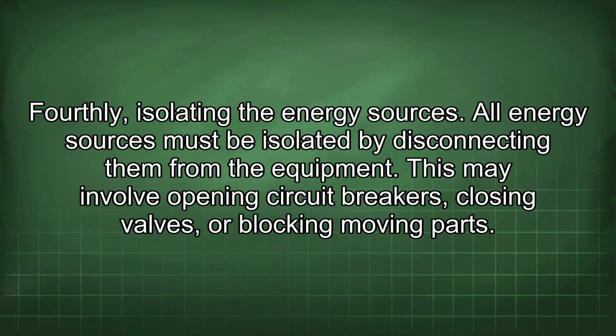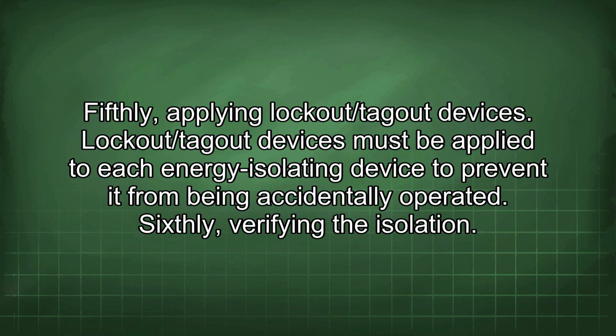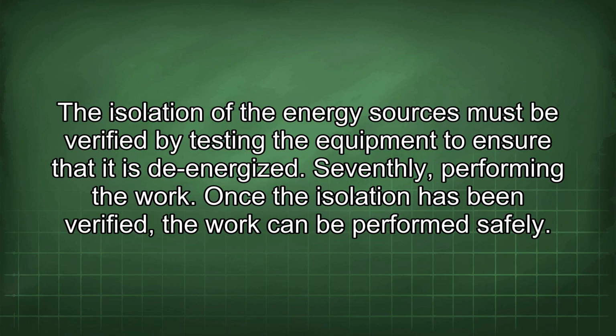Fourthly, isolating the energy sources. All energy sources must be isolated by disconnecting them from the equipment. This may involve opening circuit breakers, closing valves, or blocking moving parts. Fifthly, applying lockout/tagout devices. Lockout/tagout devices must be applied to each energy isolating device to prevent it from being accidentally operated. Sixthly, verifying the isolation. The isolation of the energy sources must be verified by testing the equipment to ensure that it is de-energized.